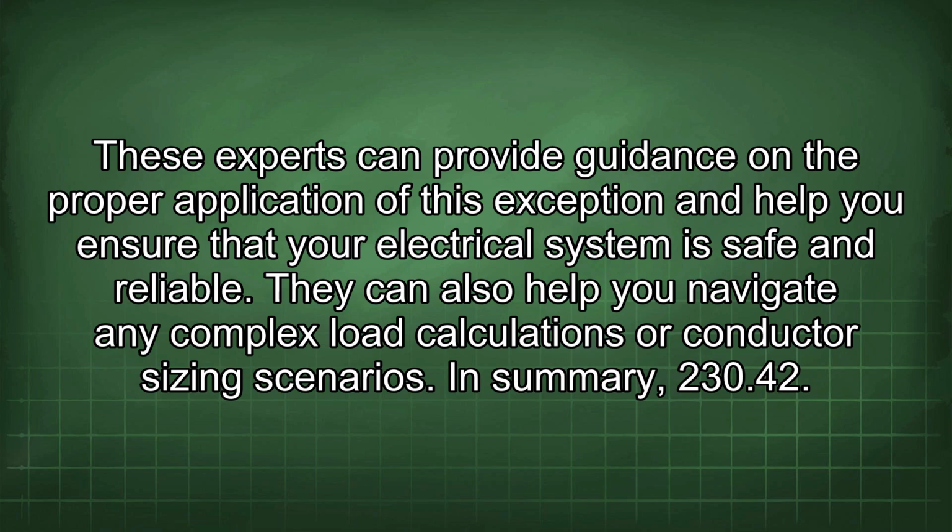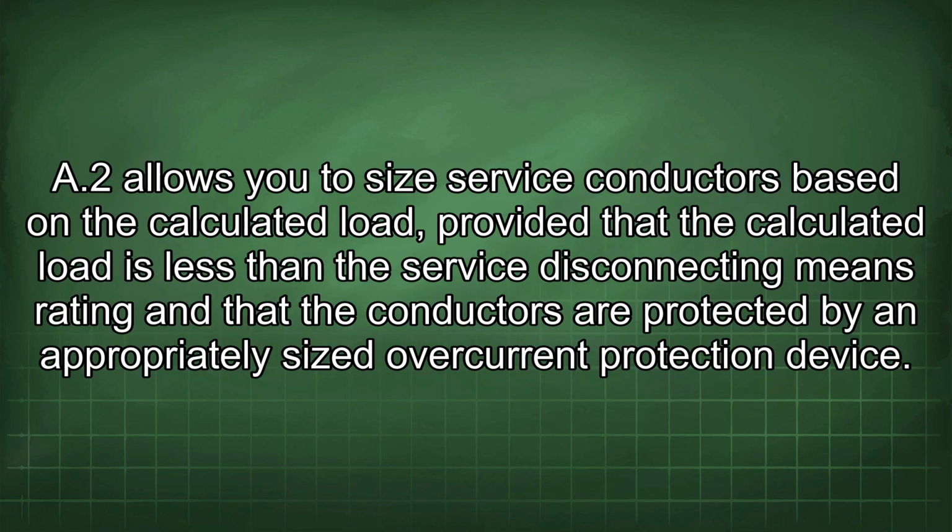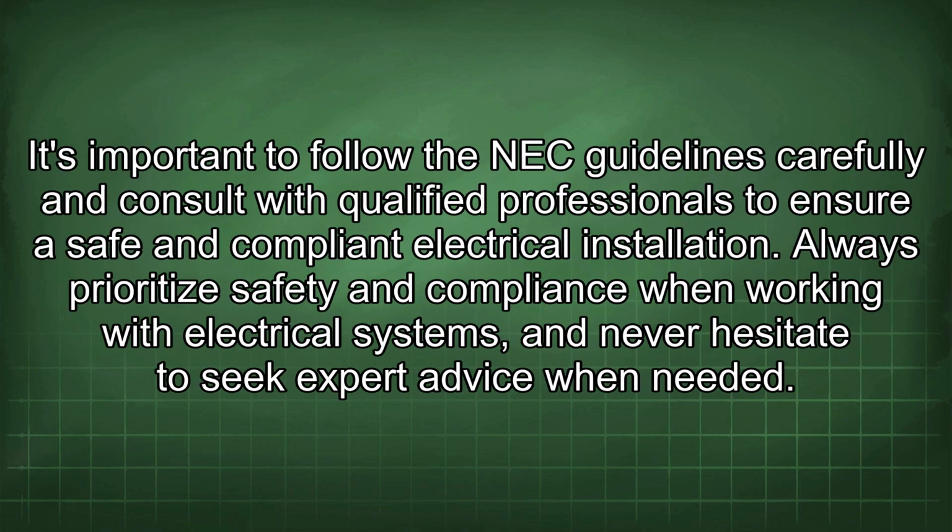In summary, 230.42(A)(2) allows you to size service conductors based on the calculated load, provided that the calculated load is less than the service disconnecting means rating and that the conductors are protected by an appropriately sized overcurrent protection device. It's important to follow the NEC guidelines carefully and consult with qualified professionals to ensure safe and compliant electrical installation. Always prioritize safety and compliance when working with electrical systems, and never hesitate to seek expert advice when needed.